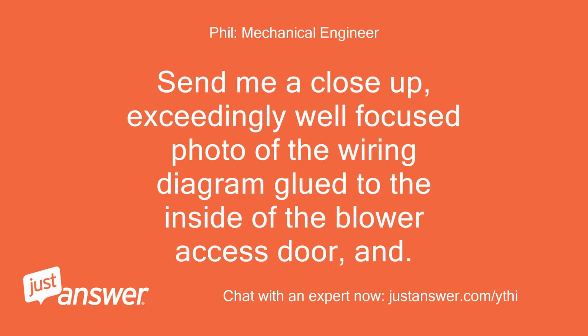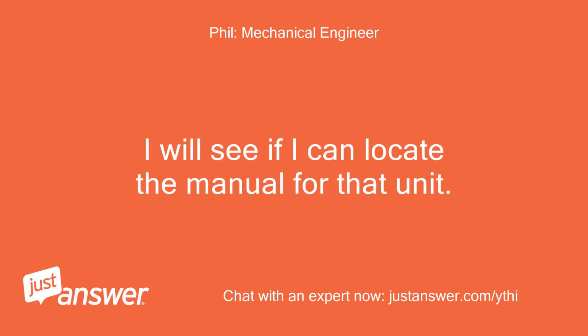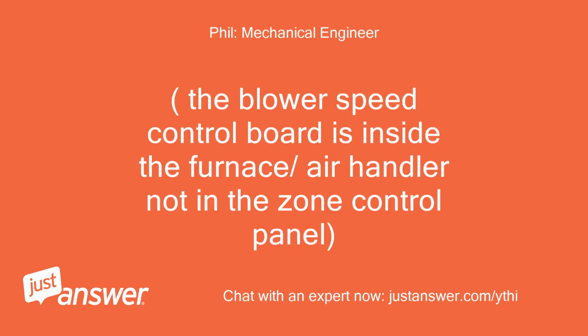Send me a close-up, exceedingly well-focused photo of the wiring diagram glued to the inside of the blower access door, and the brand name and model number of the furnace/air handler, on a tag in the same compartment as the gas valve. I will see if I can locate the manual for that unit. We can go from there. The blower speed control board is inside the furnace/air handler, not in the zone control panel.